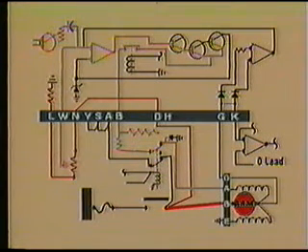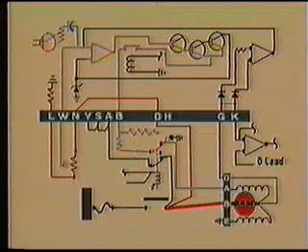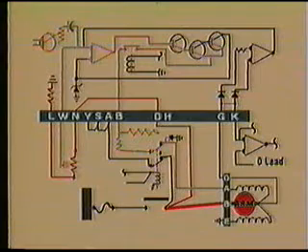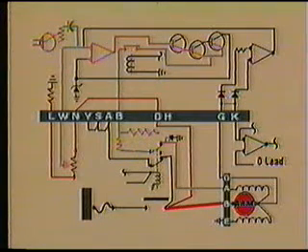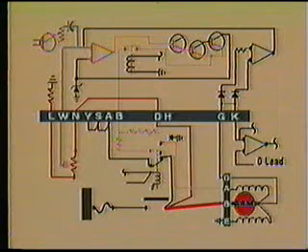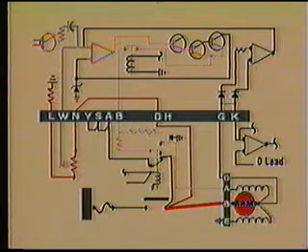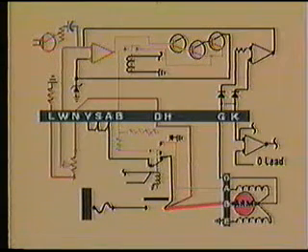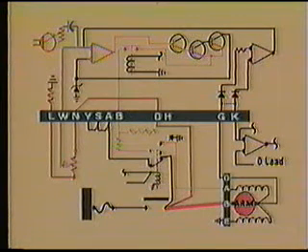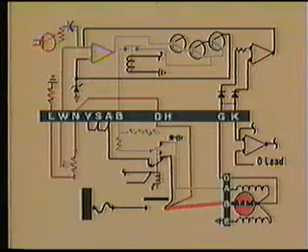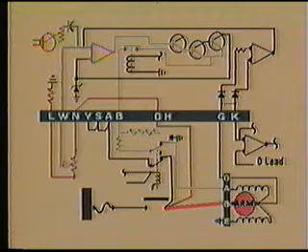This voltage makes its way to the operational amplifier, where it will at some point begin to counteract the signal provided by the oscillator circuit. The operational amplifier output will now decrease slightly, which will cause the A-lead current to decrease, which will in turn decrease the generator output. At some point, equilibrium will be reached and a regulated output is established. The generator output voltage and oscillator signal will be proportionately matched so that the operational amplifier will have a constant output.